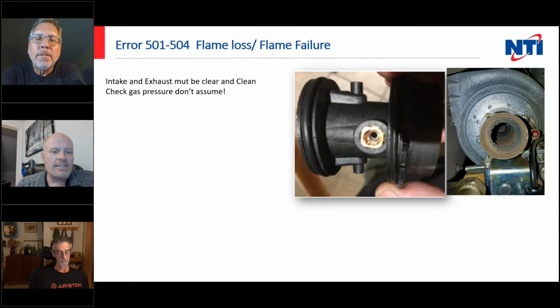Okay, we're going to go through next 501 to 504. 501 is no ignition. 504 is a flame loss during a run, but really the only difference between these two is if you have a 504, you know the igniter works, but everything else is the same. So your intake and exhaust must be clean and clear. Check for your gas pressures. Don't assume that they're good.